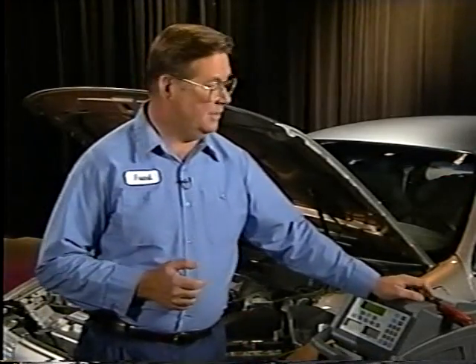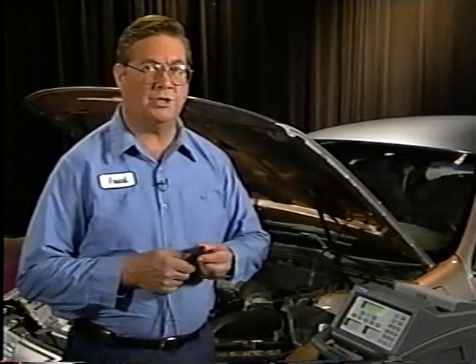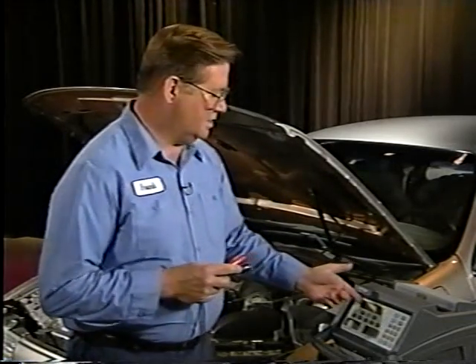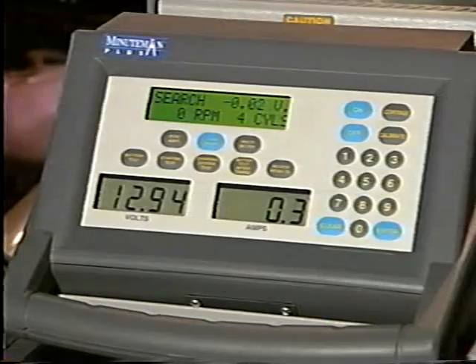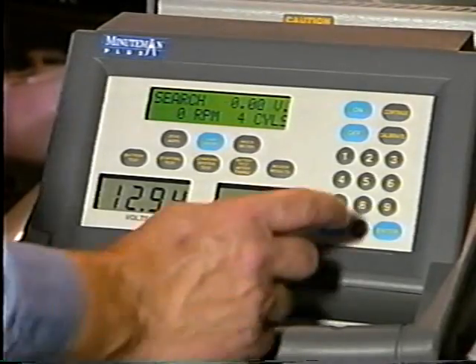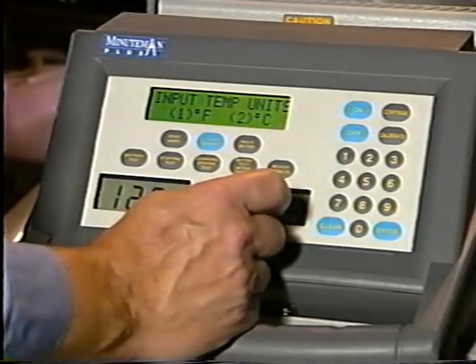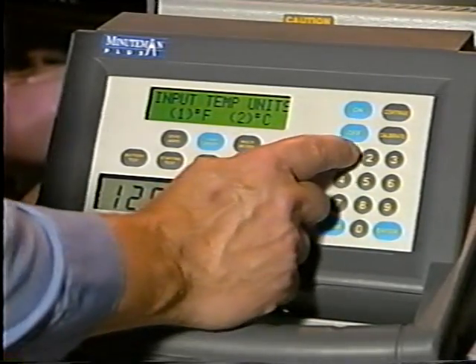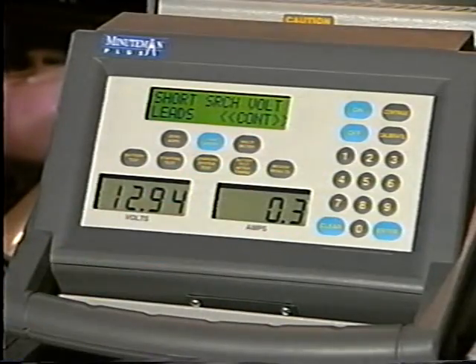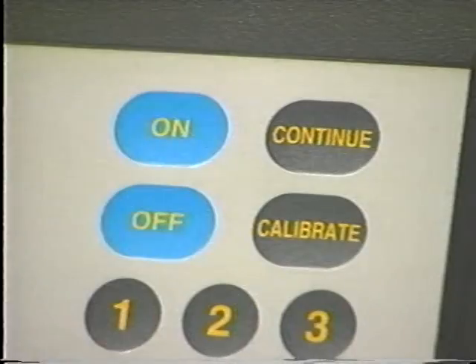Over a period of time, the leads in the Minuteman may require calibration. This action is not routine. If the message "Calibration is needed" is displayed, perform the amp zero routine. To calibrate the Minuteman, press Calibrate. The display will tell you to input temp units. Press 1 for Fahrenheit or 2 for Celsius. The Minuteman will tell you to short search the volt leads. Simply clip the search volt leads together so the metal clips are in contact with each other. Then press Continue.